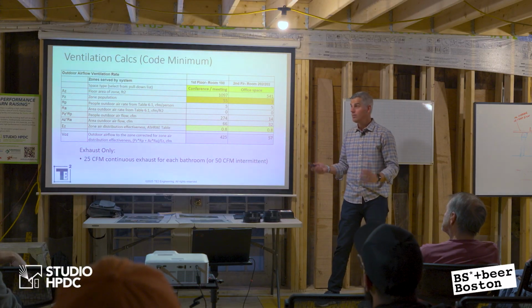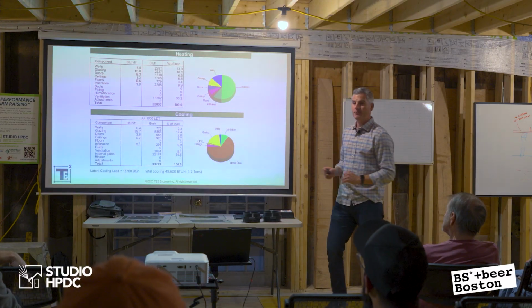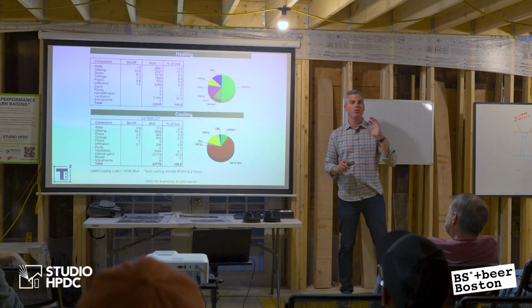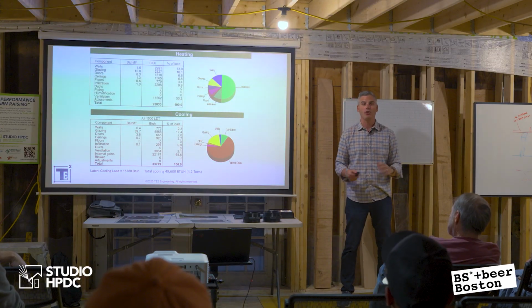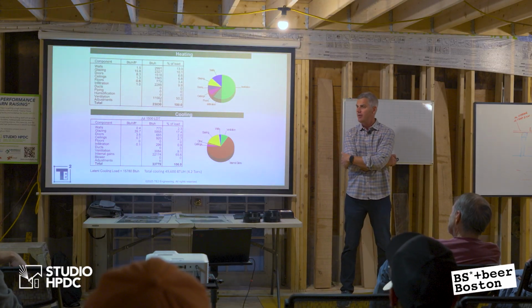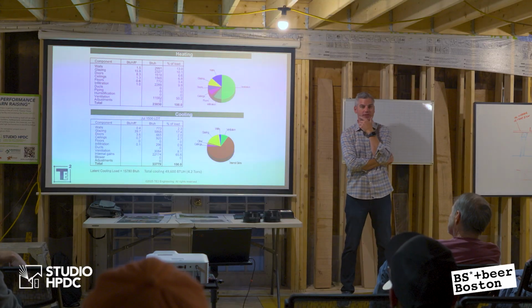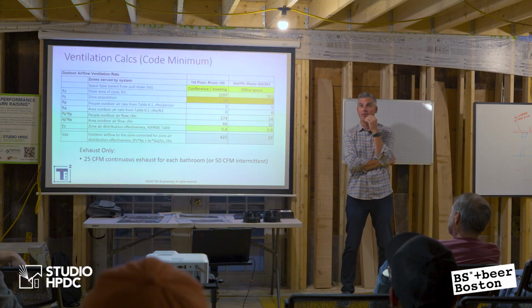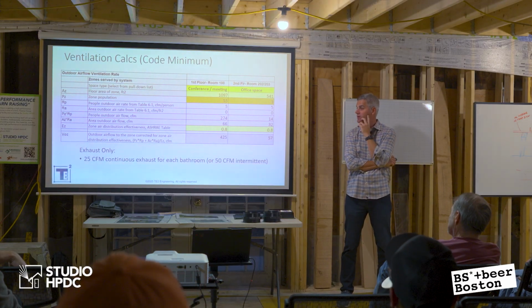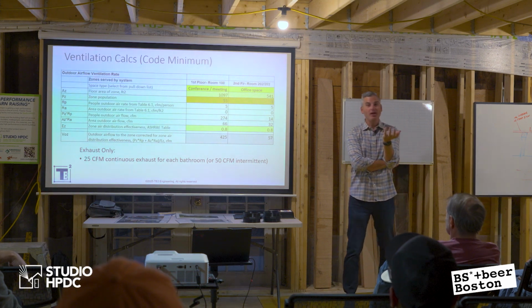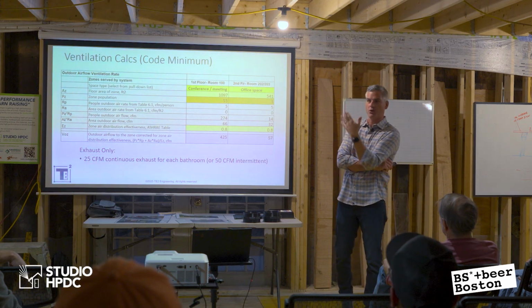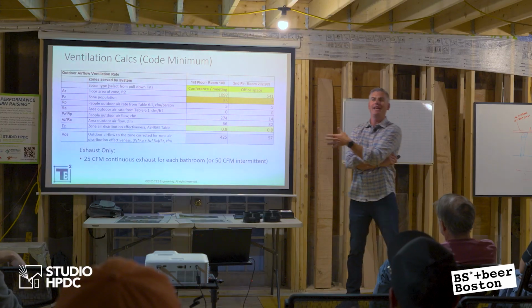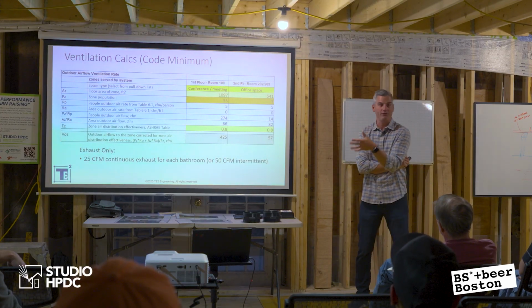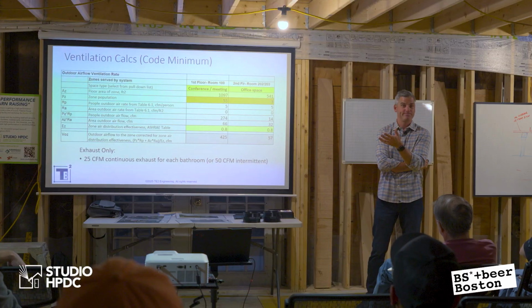With me so far? Okay, breakdown. I think Michael already mentioned this, but do you think this load of this building is heating dominant or cooling dominant? We're in a very cold climate. Is it heating dominant here or is it cooling dominant in terms of the loads in the space? Heating. Heating dominant, right? Oh, I thought I was gonna be wrong. Is it heating dominant or cooling dominant? Internal gains are pushing it to cool. So you would think most buildings in a cold climate like Boston, with a 13-degree temperature and only an 88-degree outdoor temperature, it's gonna definitely be heating dominant. Not this building.